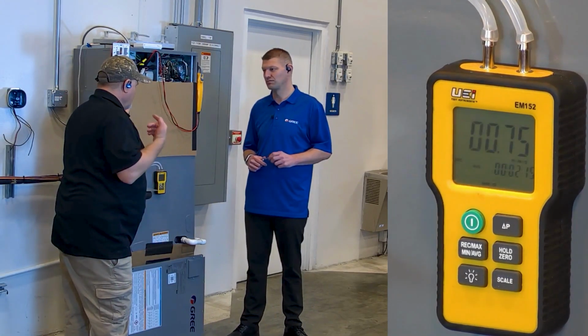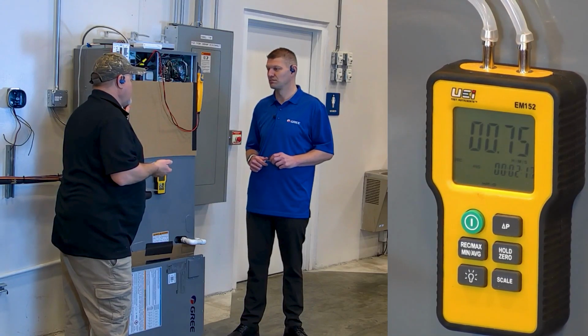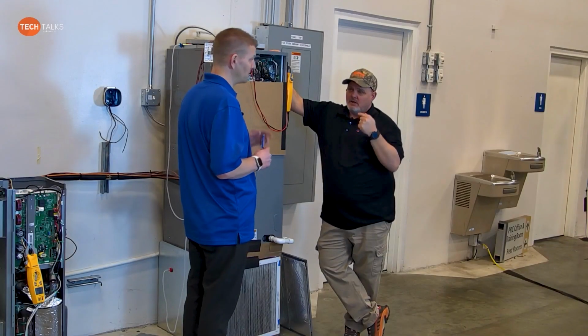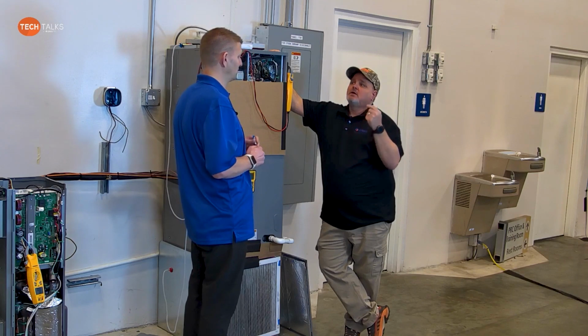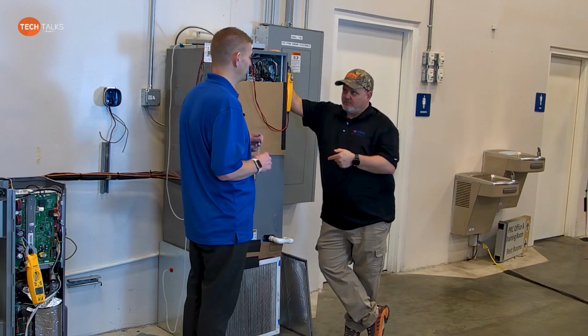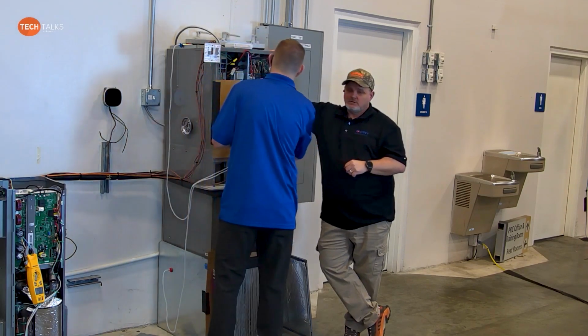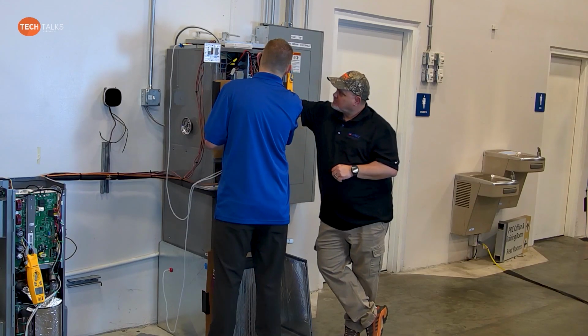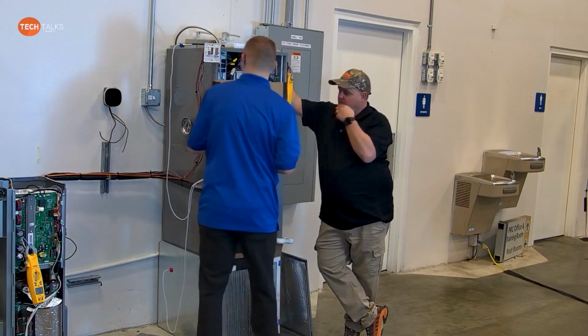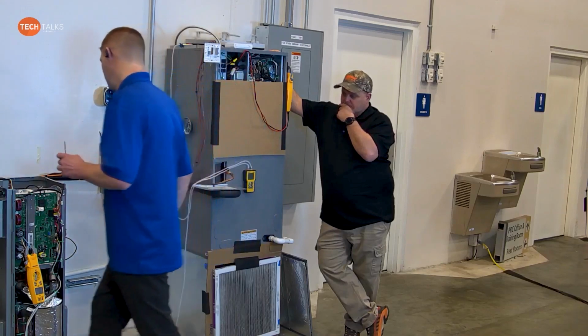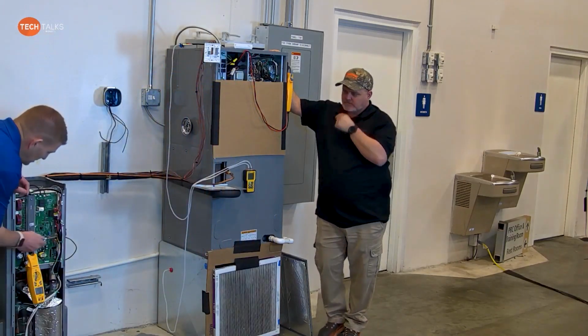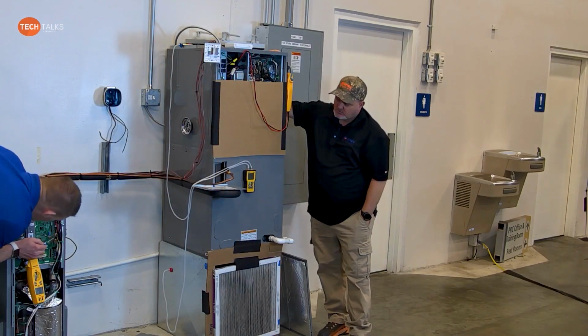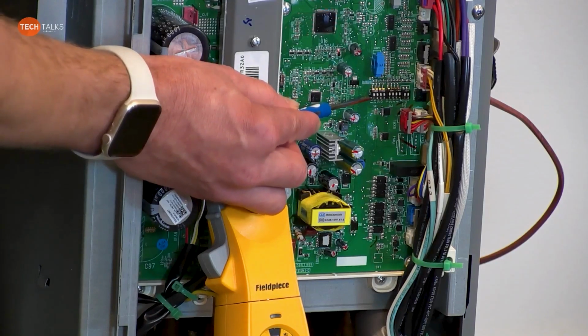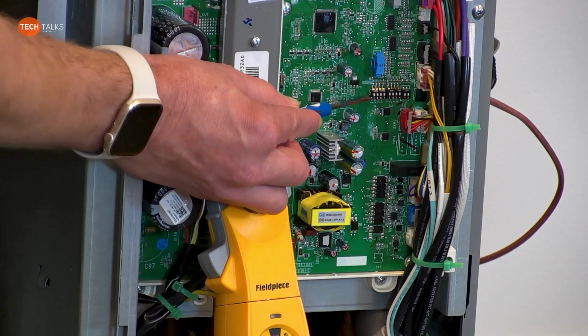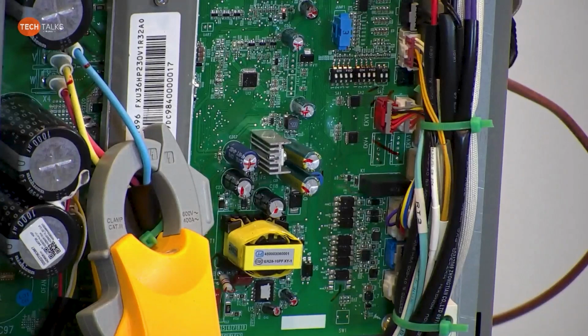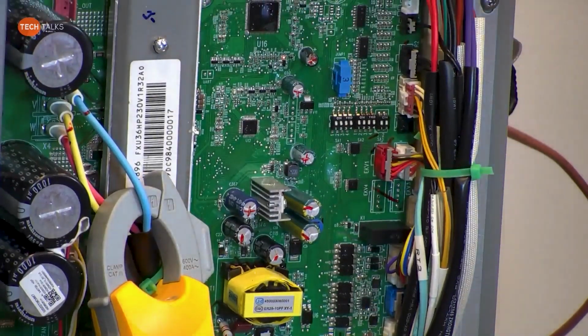All right, let's shut the system back down. SA1 dip switch number 1 needs to go to the off position. So let's go ahead and do that. And then also on the outdoor unit, right? Yep. On the outdoor unit, SA1 dip switch number 1, as you can see, is in the off position now. So that will set us up for the RS485. Okay, I'm ready. If you're ready, I'm ready. Power that up. I'll power this up.